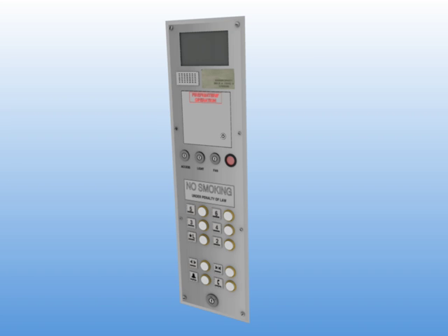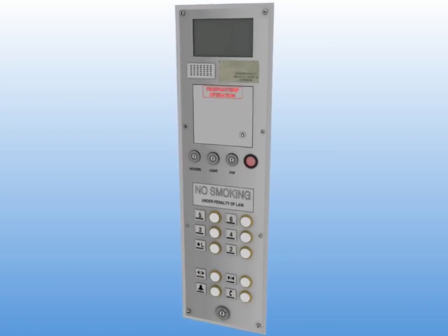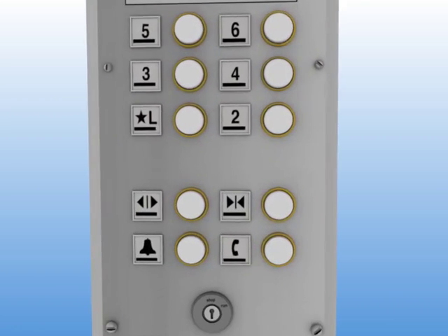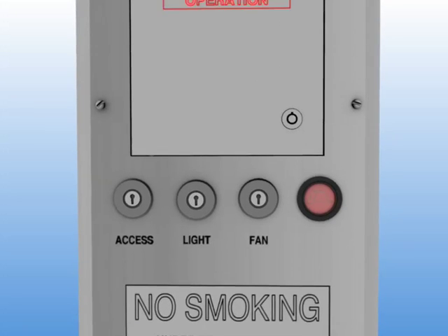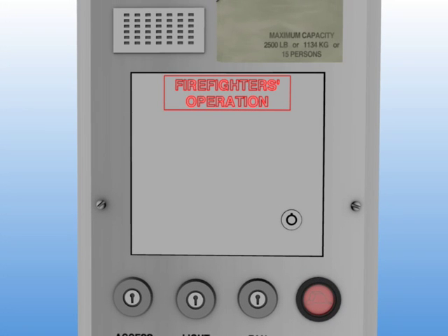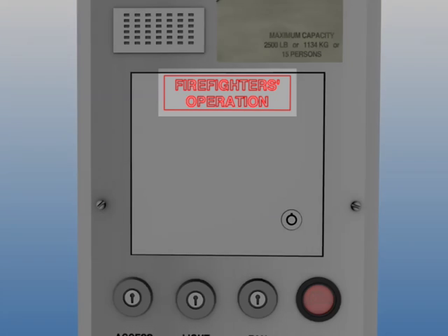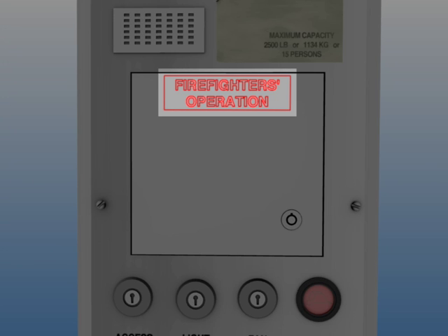This is an example of a typical car operating panel, complete with car push buttons, signage, and a firefighter's operation cabinet. Since the 2004 edition of A17.1, the fire operation cabinet has been required by code. The code also requires that the cabinet door be labeled with the words Firefighter's Operation. The lettering cannot be less than 10 millimeters high and must be red in color.